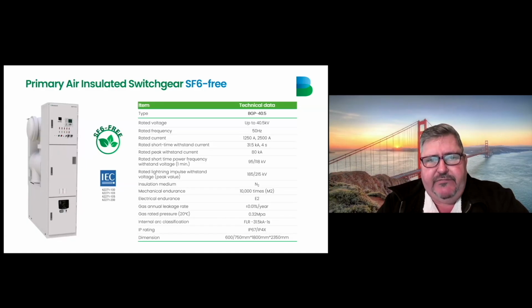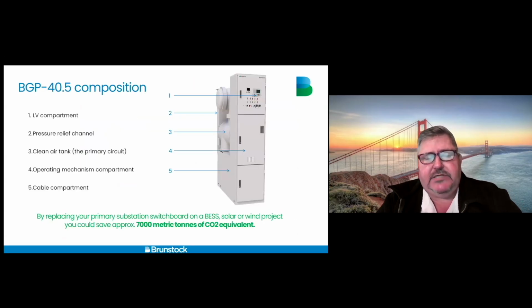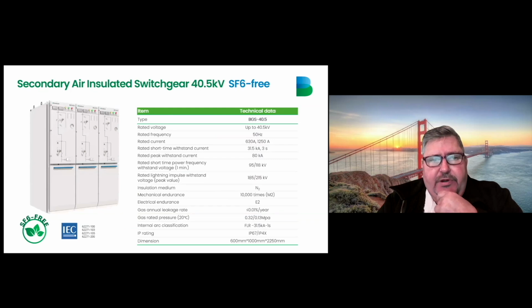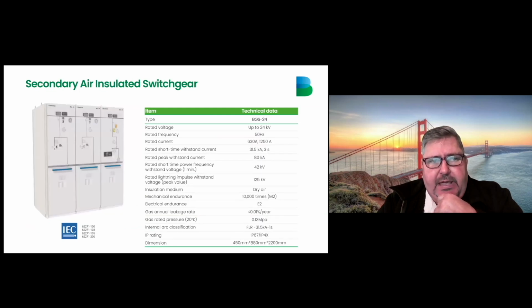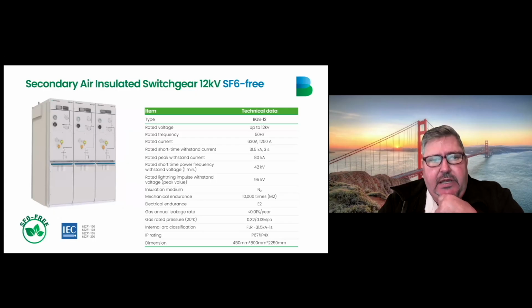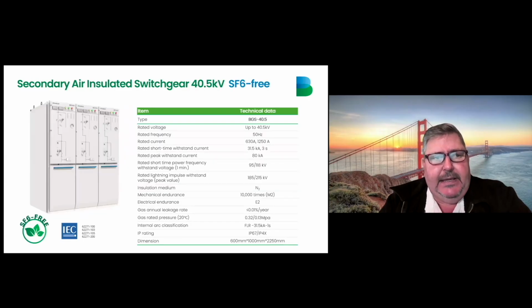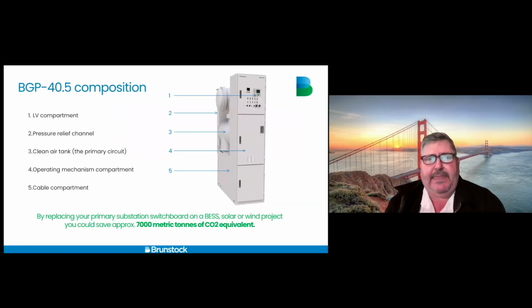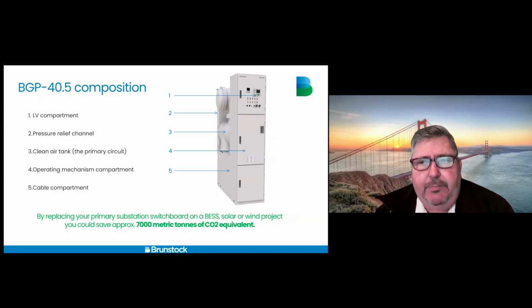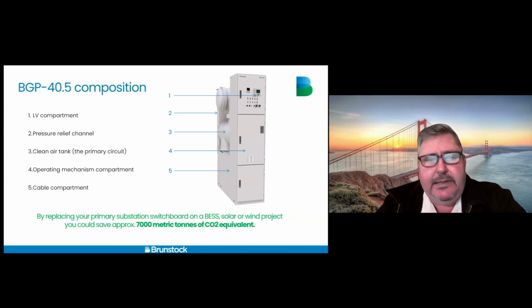For the smaller units coming from the IPP substation, Teagood also has an RMU range, which is 40.5 kV, a 24 kV unit, as well as a 12 kV unit. All of the units are rated up to 1250 amp, 31.5 kA. Now, if we go to the 40.5 kV switchgear, you'll find that it's broken down into different components. You will have a low voltage compartment for your relay, and then a pressure relief channel should there be any pressure built up in the unit itself. And then a clean air tank, which is SF6-free, obviously, the operating mechanism compartment, and then your cable compartment.